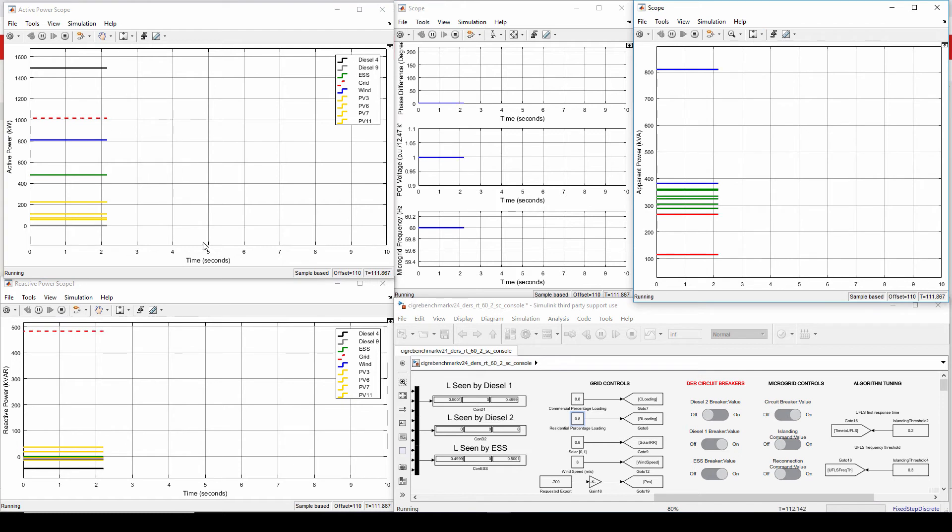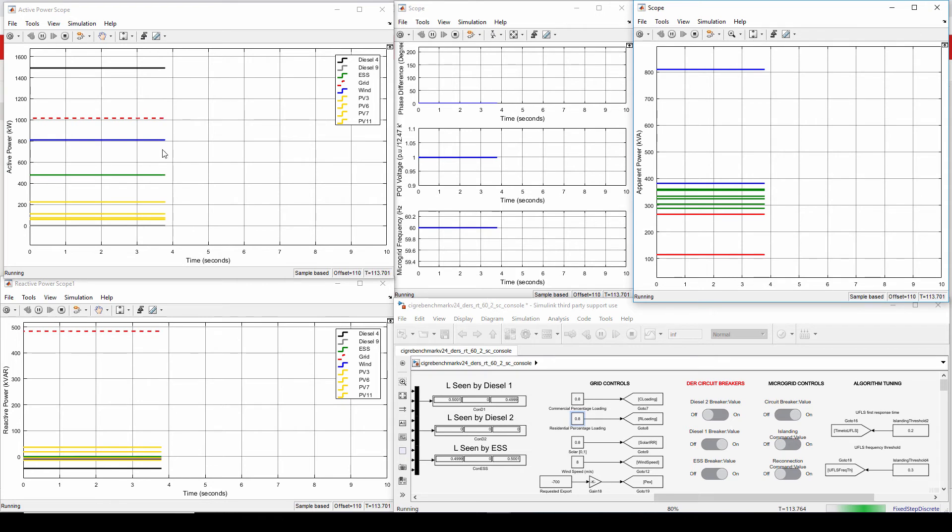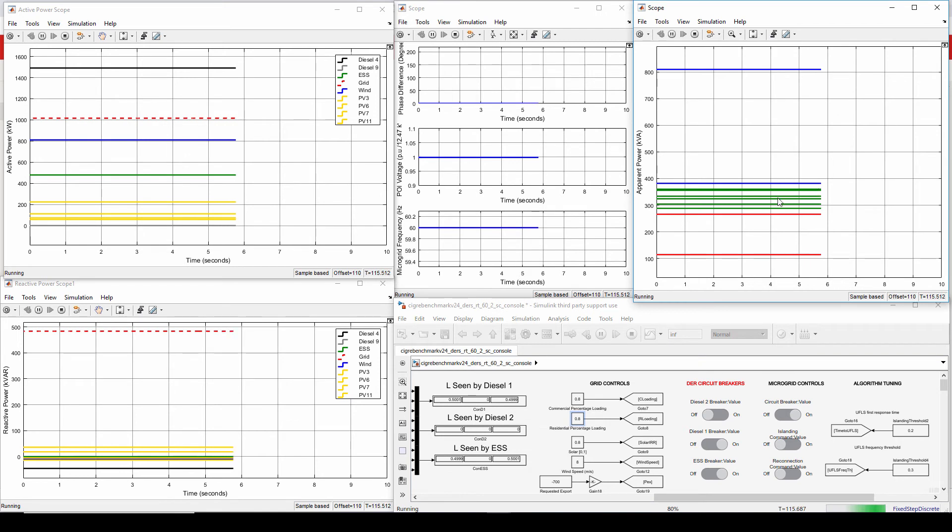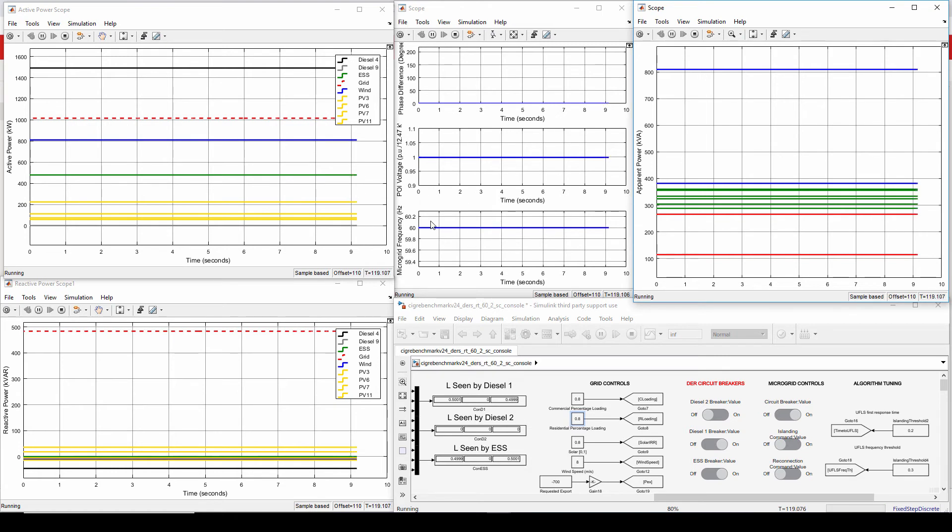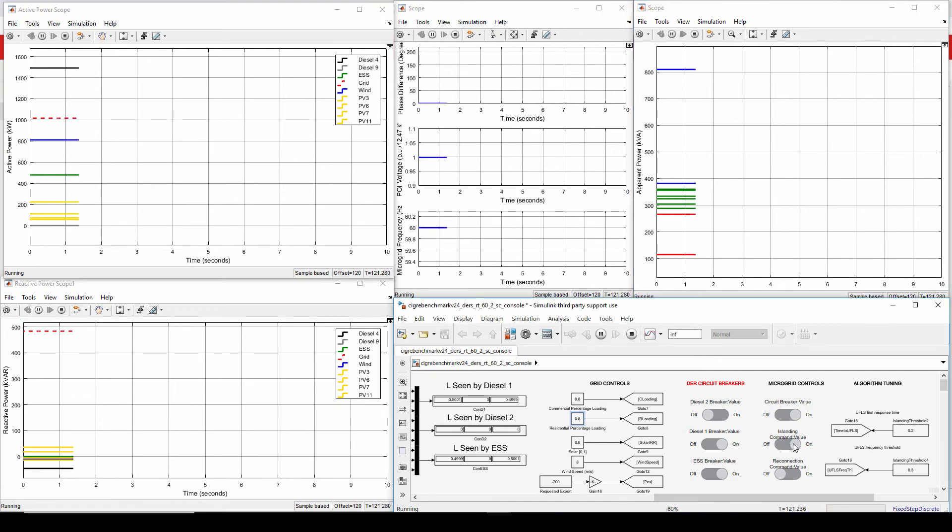So if I am to do planned islanding, the ESS and the diesel cannot cancel what remains of the POI. So that calls for the need for load curtailment. And for load curtailment, the load agents are going to distribute that remaining amount among themselves so that when I do planned islanding, they will cancel accordingly and so that I will be transitioning to islanded mode seamlessly. And I will be doing this right now.